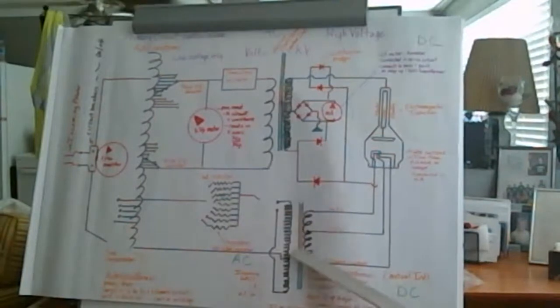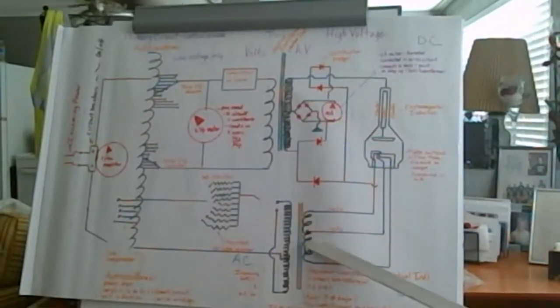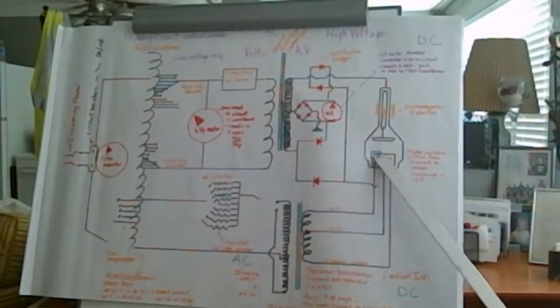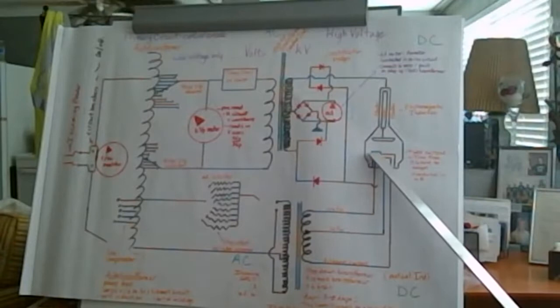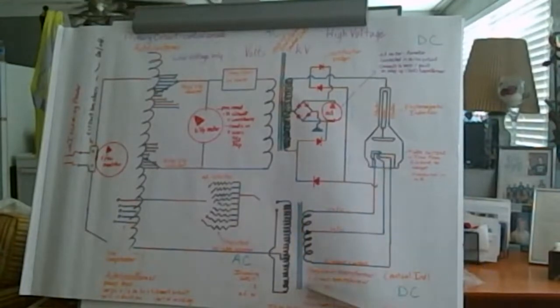Okay, so this transformer is what's responsible for getting that current to the level that's necessary to boil off the electrons. So that's our filament current, okay? And our filament current, again, is in amperes. It's about 3 to 6, and different parts of Bushong will say 3 to 8, so just so you recognize.